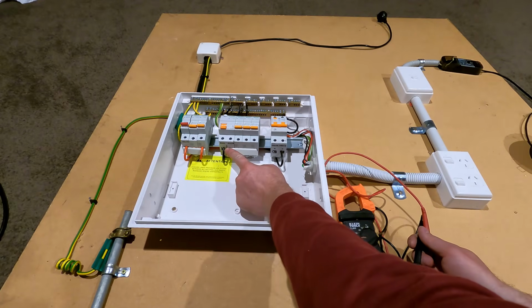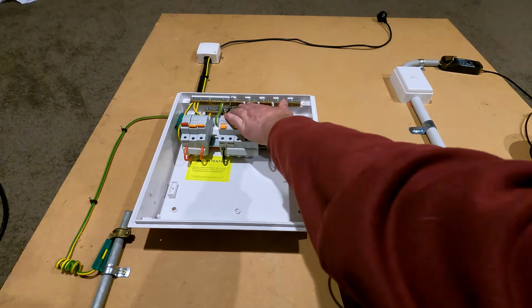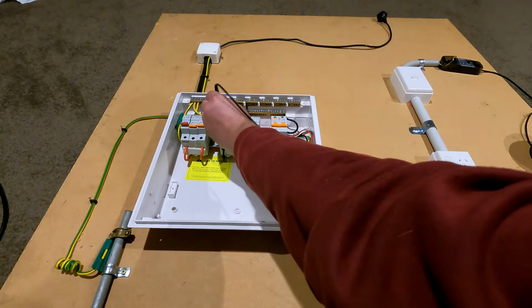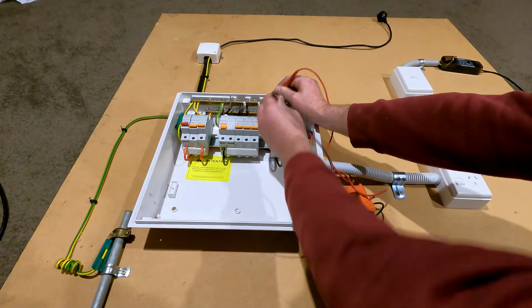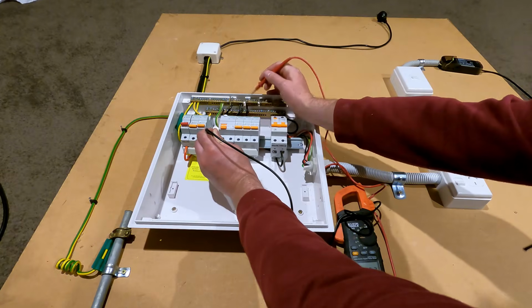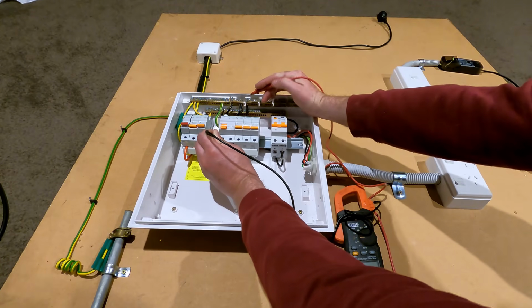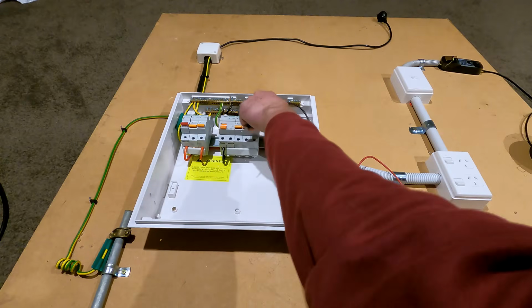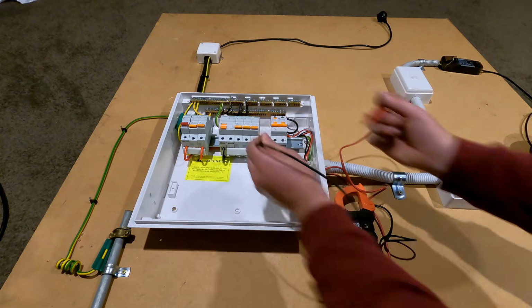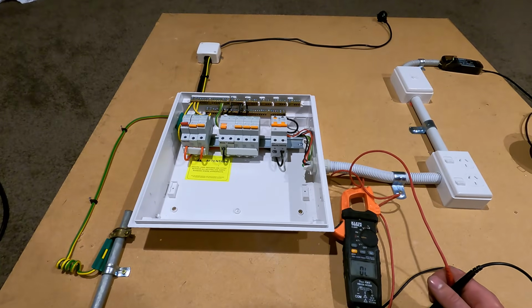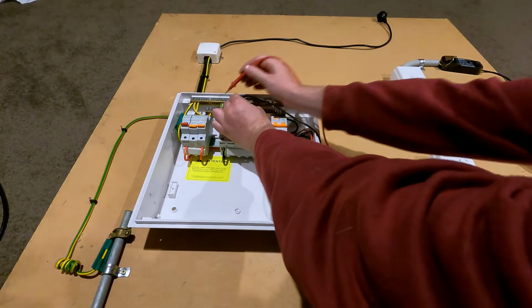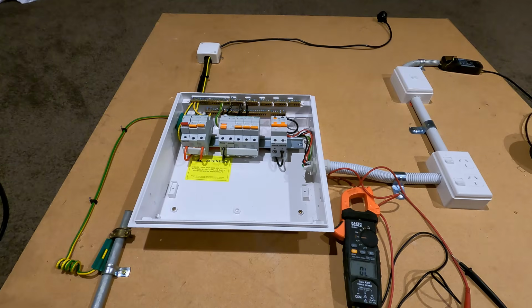The next one we'll do is we'll confirm that our load side of the RCD neutrals goes back to our RCD neutral bars, and the line side neutral goes back to the neutral bar. Cool, line side's done, load side. And we'll just test between all of the RCD neutral bars to make sure that none of them are interconnected somewhere. And then the last thing we'll want to confirm is that the MEN link is intact. Perfect. So now we are ready to liven. I'm happy that this installation's safe to liven.